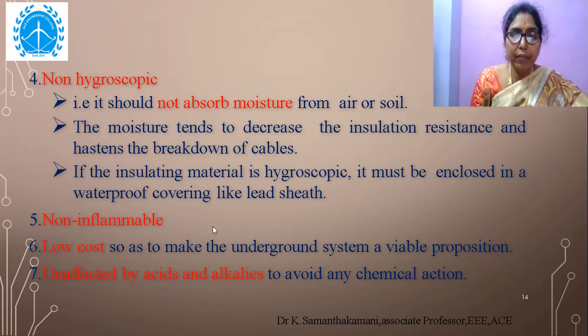We will place these cables either in air or in soil, so it should not allow any moisture content into the cable. If moisture enters the cable, the insulation resistance of the cable decreases, so there is a chance of breakdown of the cables. So the non-hygroscopic nature of the insulating material is a must.